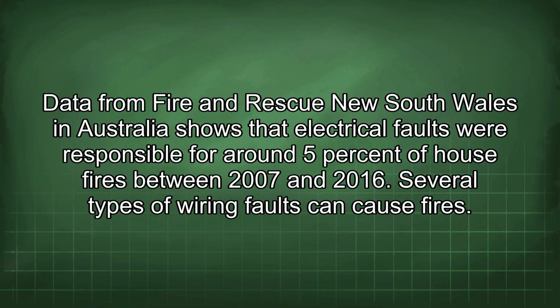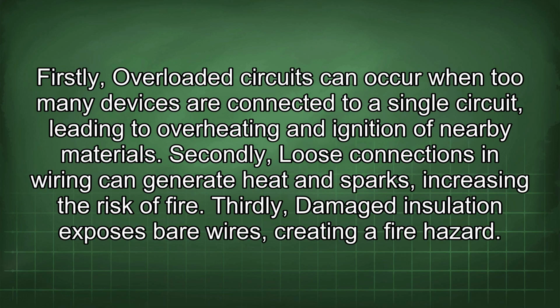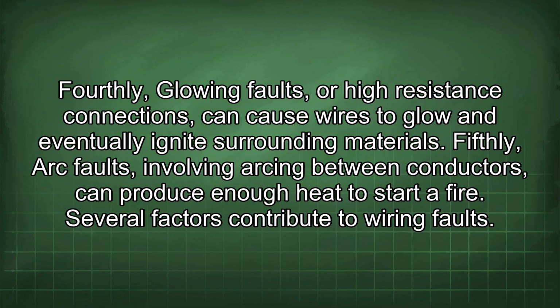Several types of wiring faults can cause fires. Firstly, overloaded circuits can occur when too many devices are connected to a single circuit, leading to overheating and ignition of nearby materials. Secondly, loose connections in wiring can generate heat and sparks, increasing the risk of fire. Thirdly, damaged insulation exposes bare wires, creating a fire hazard. Fourthly, glowing faults, or high-resistance connections, can cause wires to glow and eventually ignite surrounding materials. Fifthly, arc faults, involving arcing between conductors, can produce enough heat to start a fire.